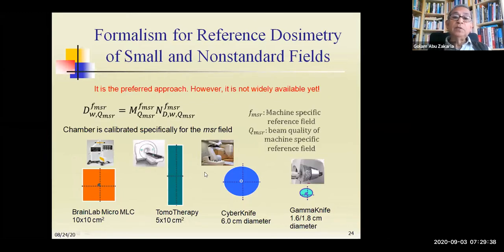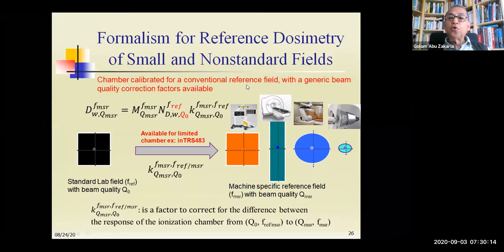Here I will show you three formalisms. This is the first. You can calculate the dose for the MSR field when you know the readings in the MSR field, and there is a calibration coefficient for the MSR field. This is the simpler way to calculate the dose, but it is not easy, because we have no data for this in MSR, because the primary labs have not such types of machines, so they cannot determine these values. So the second one is important. This is actually chamber calibration in the conventional reference field with a generic quality correction. That means you calculate the dose in these machines, but take the value of the calibration coefficient for the conventional field, what you know from 398, and you just correct it through these factors.